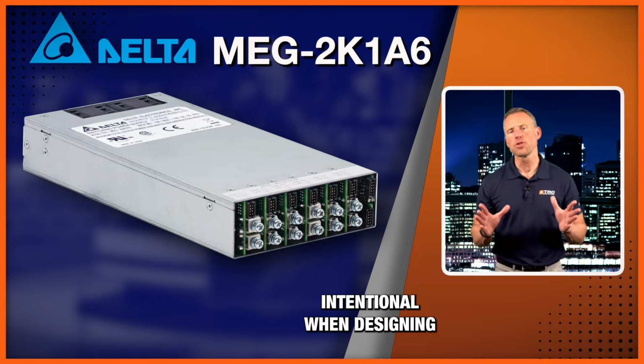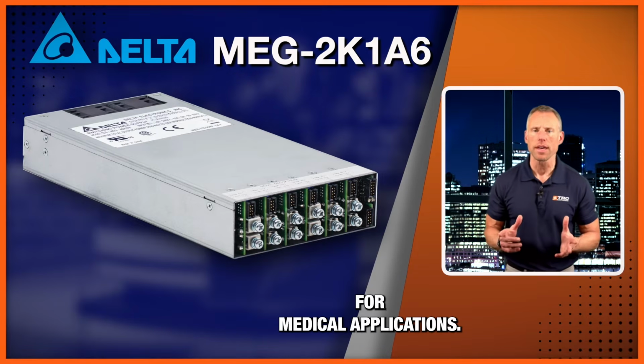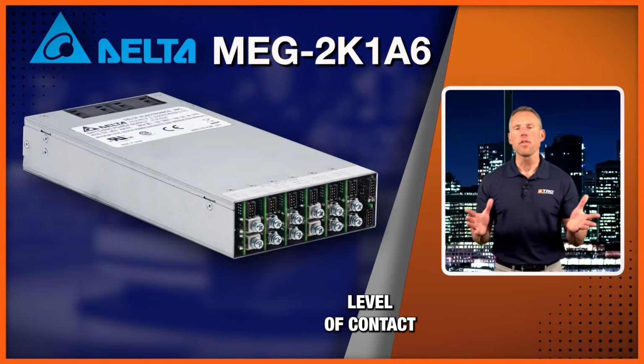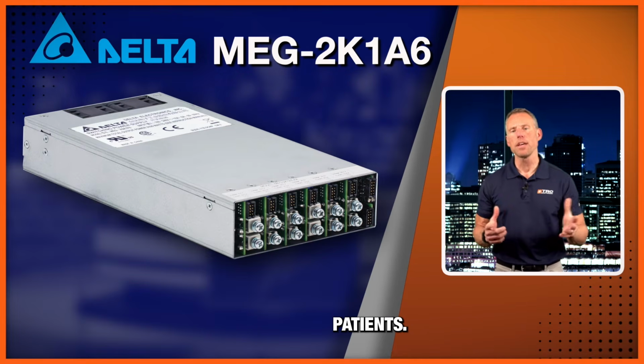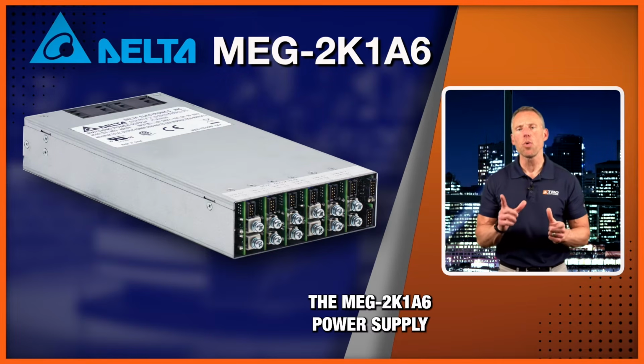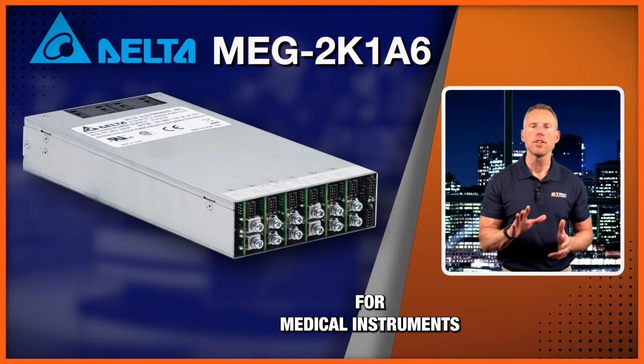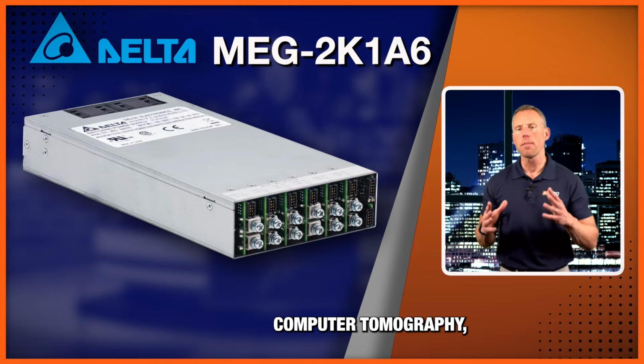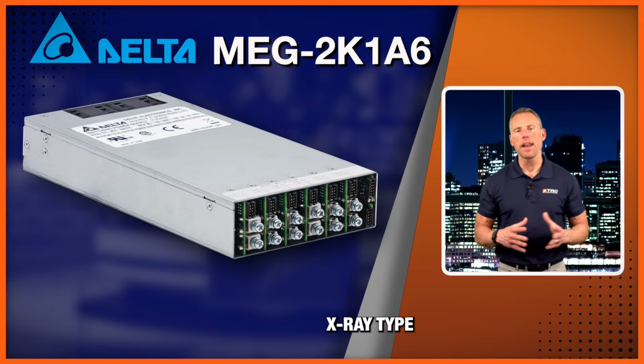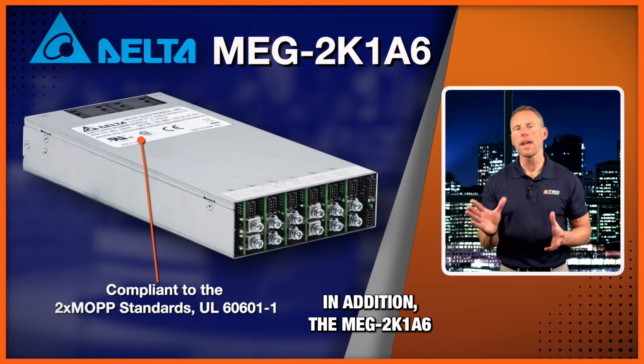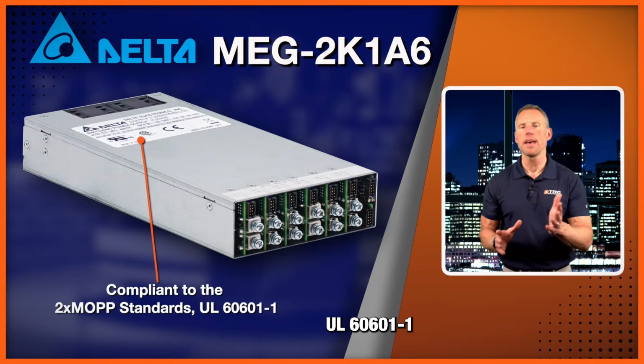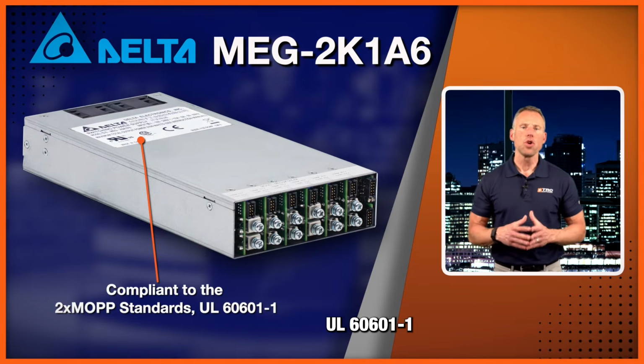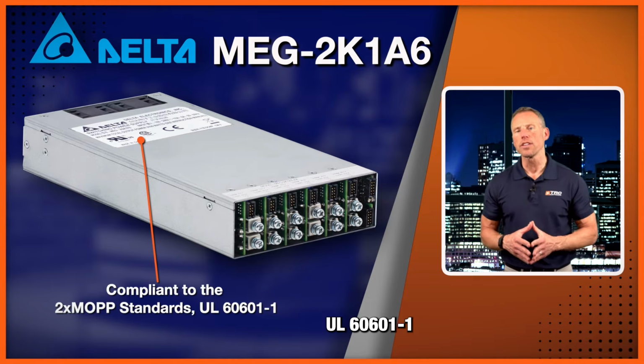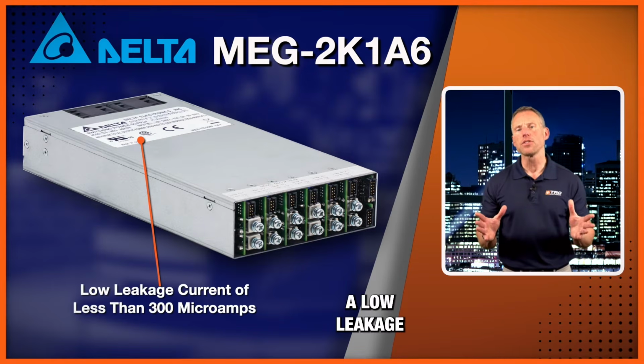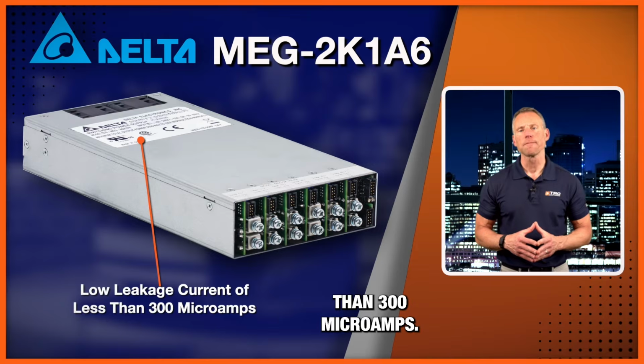Delta was intentional when designing this power supply for medical applications, considering a high level of contact between medical equipment and patients. The MEG-2K1A6 power supply is suitable for medical instruments such as computer tomography, surgical equipment, and X-ray type machines. In addition, it complies with 2x MOPP standards, UL 60601-1, and has a low leakage current of less than 300 microamps.